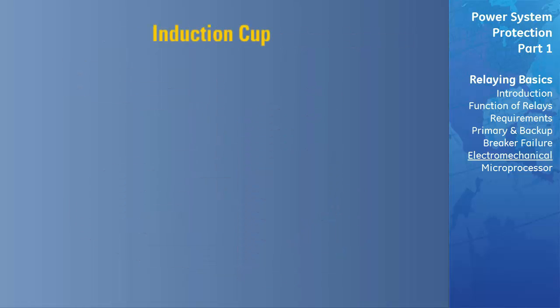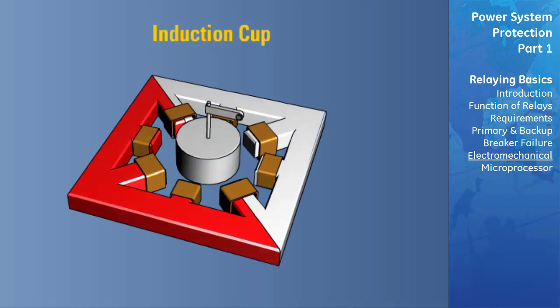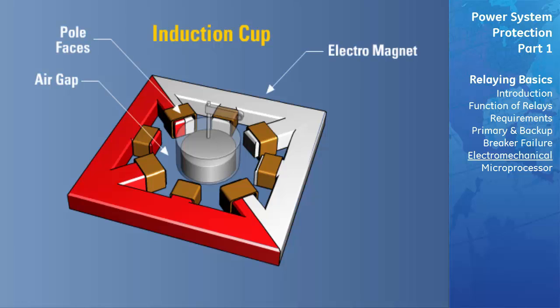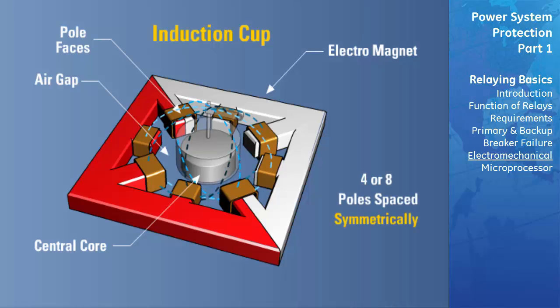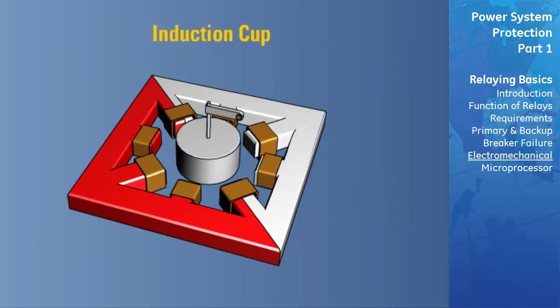The induction cup element consists of a metallic cylinder with one end closed like a cup. The cup rotates in an annular air gap between the pole faces of electromagnets and a central core. The induction cup unit uses four or eight poles spaced symmetrically about the circumference of the cup. Due to the low inertia of the rotating parts of the relay, this style is capable of high-speed operation. Hence, it is used for functions requiring instantaneous operation. The multiplicity of poles also permits measurement of more than one electrical quantity.